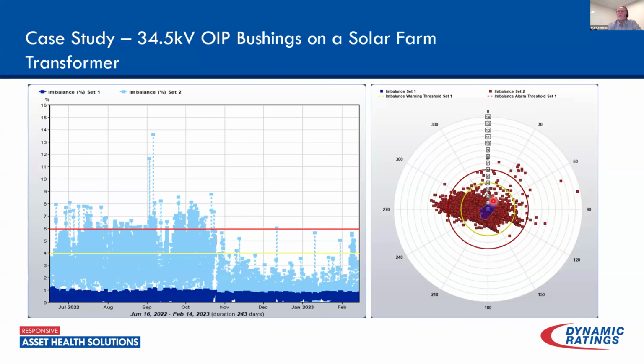I can see on my high side that I've got a very tight pattern. Basically, I'm running a sum of current method here. But you can see on the low side, I've got almost a scatter plot. I see a lot of activity. Now, this isn't surprising when we saw the voltage fluctuations in the megawatt flow and megavar flow on the system. So I think this is some of what's driving the activity on that bushing monitor right now. What we can see is that the high side is definitely doing good, but on the low side it's really hard to predict which bushing is having a problem, or is any bushing, or is this all just system related?